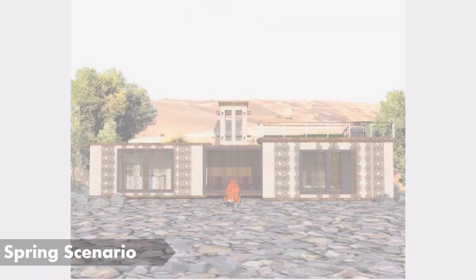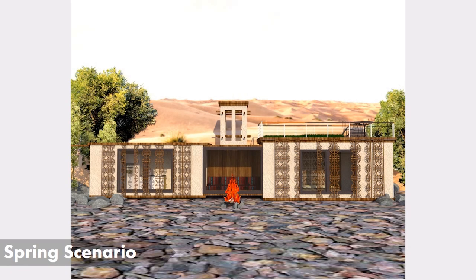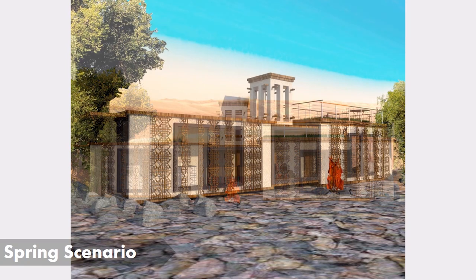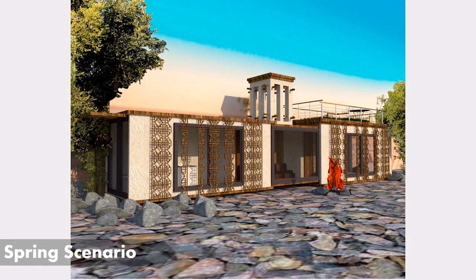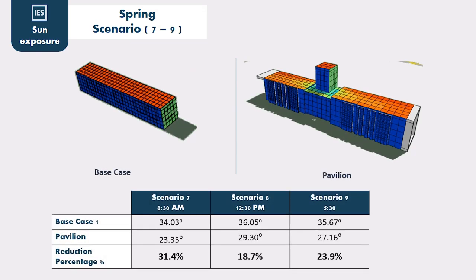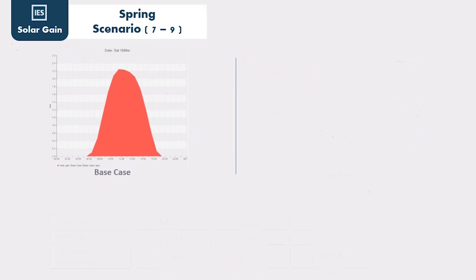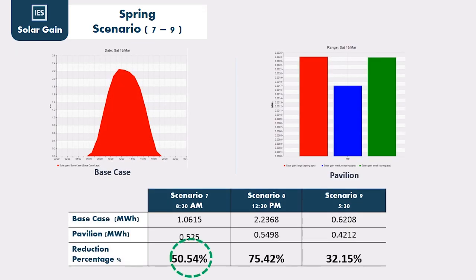For the spring scenario, we used moderate techniques. We kept the Burjeel to maintain cool airflow inside, kept Mashrabia panels apart when sun is needed and moved them closer to block it, and the east shading device moved inward following our shading study. For sun exposure, we managed to reduce air temperature by 31% in Scenario 7, 18.7% in Scenario 8, and 23.9% in Scenario 9. Solar gain was reduced to less than 50% in Scenario 7, 75% in Scenario 8, and 32% in Scenario 9.